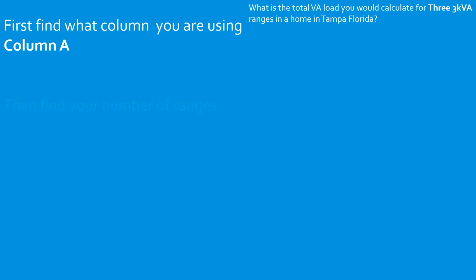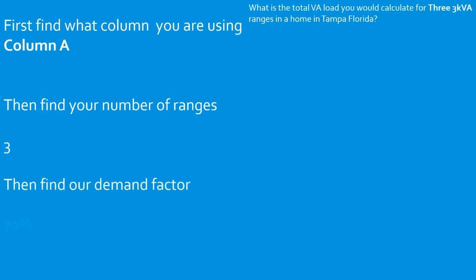So now we go down and find our number of ranges on the left-hand side, and we come over and tee off and find our demand factor. So we have 3 ranges. We're going to find out that our demand factor is 70%. Now what we can do is actually start from scratch.